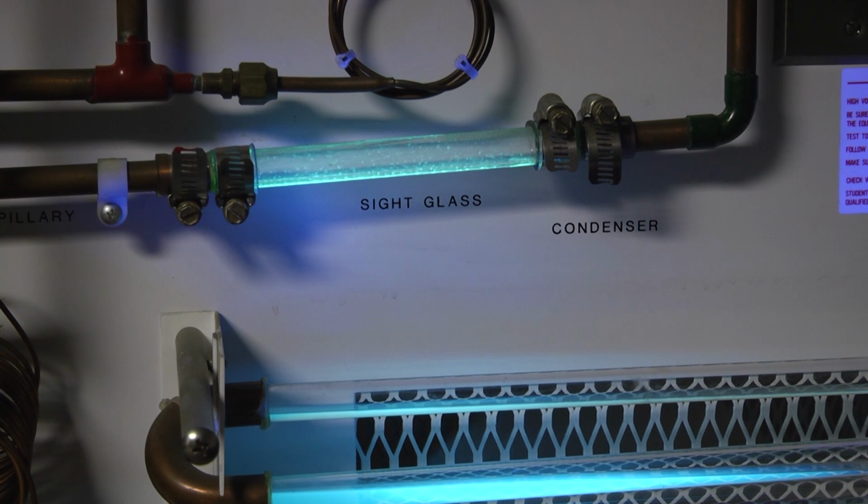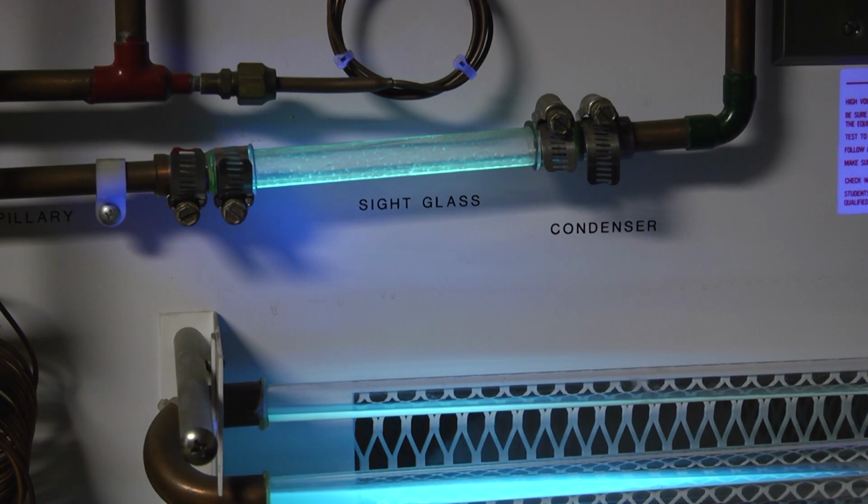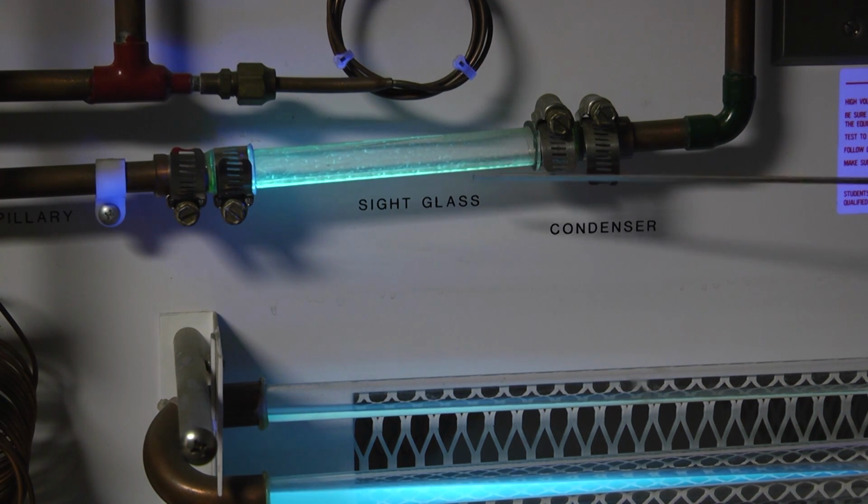Now that the refrigerant's traveled through the evaporator and it's become 100% superheated gas, it goes to the compressor. And as its name suggests, the compressor compresses the refrigerant. By compressing it, it does two things. It raises its pressure, and it also raises its saturation temperature. And again, saturation temperature is the point at which the refrigerant will either condense or evaporate, the point where it's ready to change state. What we're seeing here is the discharge line leaving the compressor. And as we look at the tube, we can tell that there's no liquid refrigerant present.